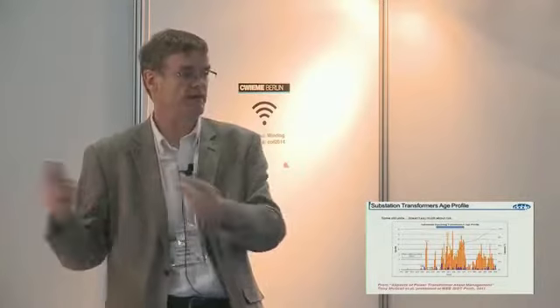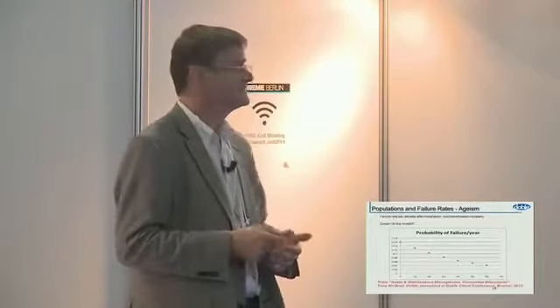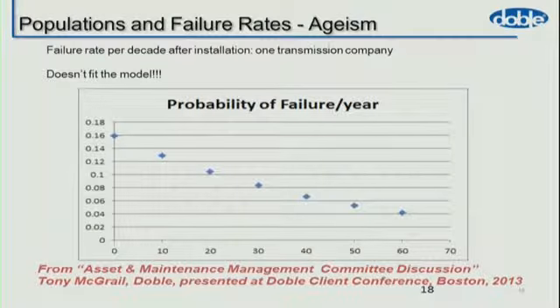Unless you have those two-thirds of external causes - lightning, vandalism, system faults - but even then, they're built big. So what we found was that the probability of failure during the first 70 years starts high and fades away. It's the start of a bathtub curve. The likelihood is, by the time you get to the bottom of that curve, random failures just take over and you won't see the far end. But we're seeing 60, 70, 80-year-old transformers, and the failure rate for that population is not increasing.